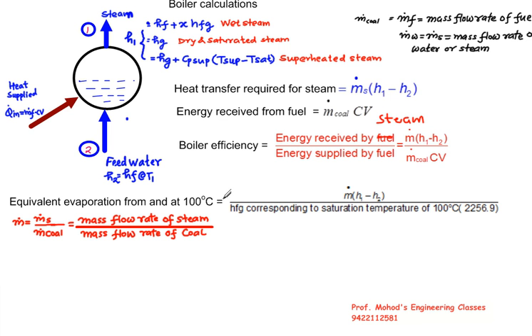Equivalent evaporation from and at 100 degree Celsius is M dot into H1 minus H2 upon HFG corresponding to saturation temperature of 100. From steam table this value is approximately equal to 2256.9. Mass M dot here is basically ratio of mass flow rate of steam upon mass flow rate of coal.